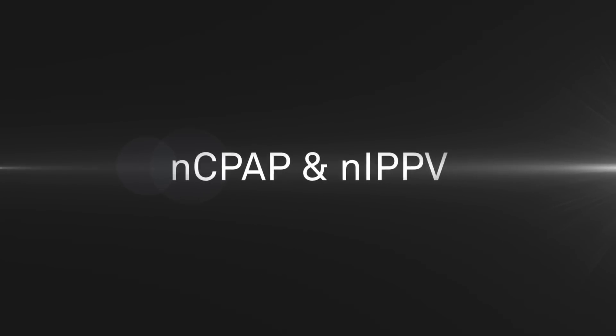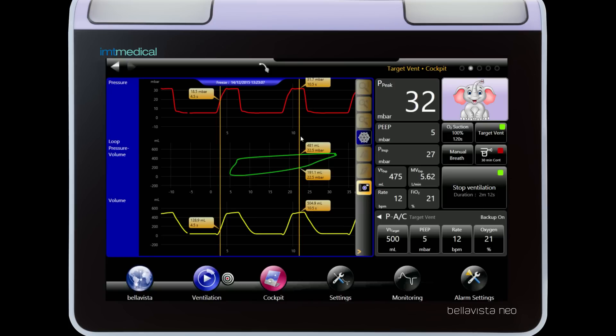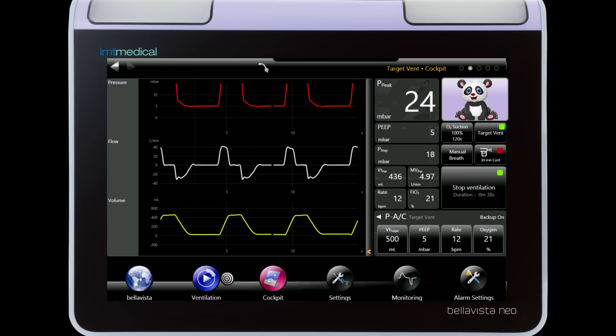The nCPAP mode features a breath rate detection and gives you additional safety through apnea alarming. TargetVent provides a full ventilation platform with target volumes for extremely low birth weight patients.